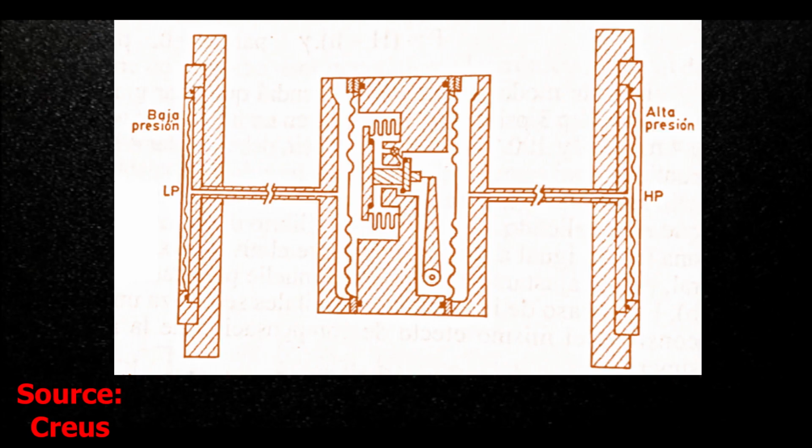When fluid can vaporize at room temperature and operating pressure, the equalization line can be plugged if the fluid is not clean. To solve this, the line can be purged, but this is not recommended due to the maintenance problems and possible loss of accuracy. Then, another option would be to use a differential pressure transmitter attached with two capillaries to two diaphragms connected at the top and bottom of the tank. It is important that both diaphragms are at the same temperature to avoid measurement errors due to the expansion of the fluid contained in the capillary tube.